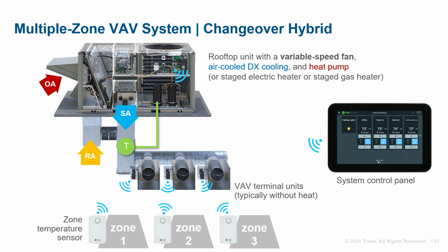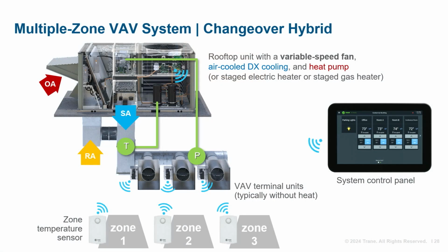The controller on each VAV terminal votes based on the cooling or heating need of its zone. This means that the rooftop unit is providing only cool air for cooling or warm air for heating. This is the successor to the older changeover bypass system. So in the cooling mode, the variable speed fan modulates to maintain duct static pressure at a programmed set point, while the cooling capacity is modulated or staged to maintain the discharge air temperature set point.